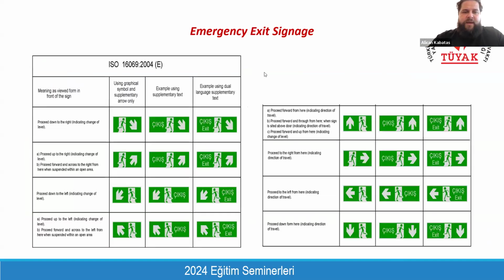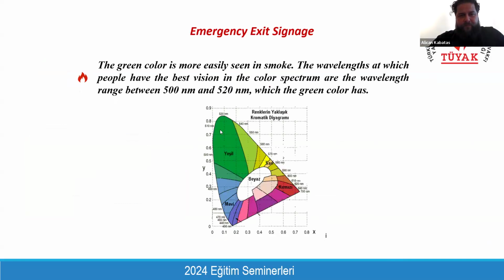According to the Turkish fire code, it should be these types. The background is green and the pictograms are on white. This is not by chance. When you see the spectrum of visibility according to the colors within the smoke, the green color is the most easily seen spectrum. It has the larger spectrum. That's why the exit signage is determined to have a green background and white pictogram. That's why we cannot change it. It is written in the Turkish fire code, even if it is not parallel to your interior architectural design.